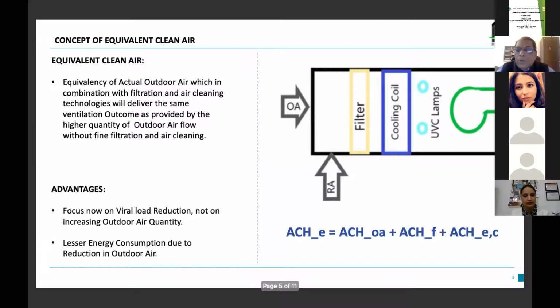In that case, suppose you require to control the viral load, the bacteria and viruses in the space. Suppose you require 1000 CFM to attain 3 air changes per hour of outdoor air in the space. Presently, if you want 1000 CFM, and then you add to this AHU filtration and air cleaning technologies, these air cleaning technologies will offset the additional requirement of outdoor air. So your outdoor air requirement reduces, and suppose you have reduced it from 1000 to 300 CFM.